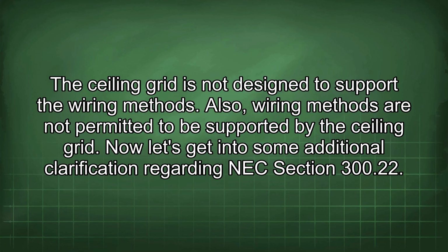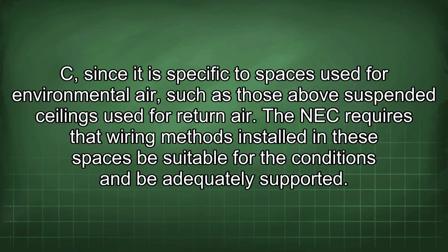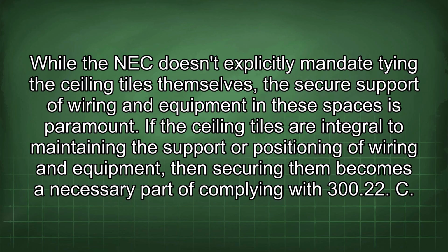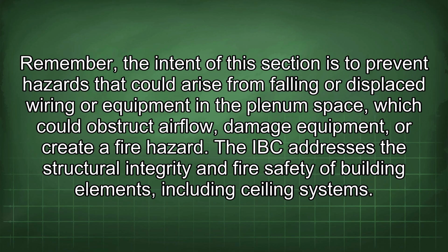Now let's get into some additional clarification regarding NEC Section 300.22(C), since it is specific to spaces used for environmental air, such as those above suspended ceilings used for return air. The NEC requires that wiring methods installed in these spaces be suitable for the conditions and be adequately supported. While the NEC doesn't explicitly mandate tying the ceiling tiles themselves, the secure support of wiring and equipment in these spaces is paramount. If the ceiling tiles are integral to maintaining the support or positioning of wiring and equipment, then securing them becomes a necessary part of complying with 300.22(C). Remember, the intent of this section is to prevent hazards that could arise from falling or displaced wiring or equipment in the plenum space, which could obstruct airflow, damage equipment, or create a fire hazard.